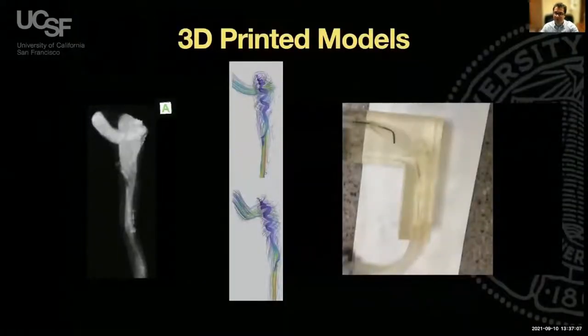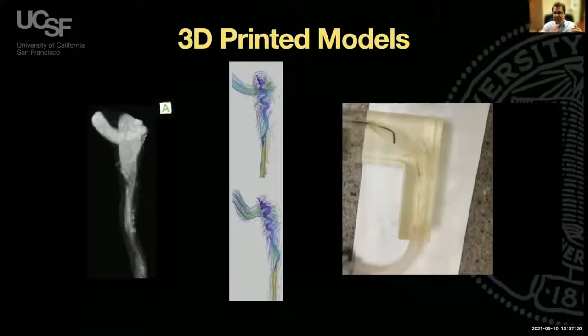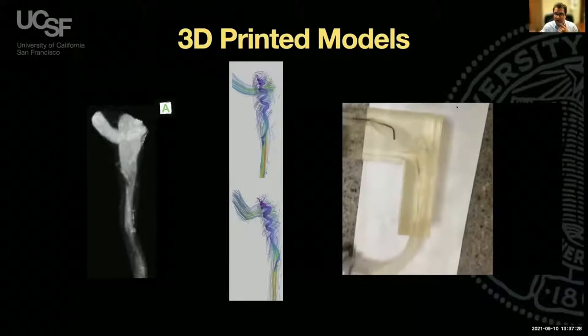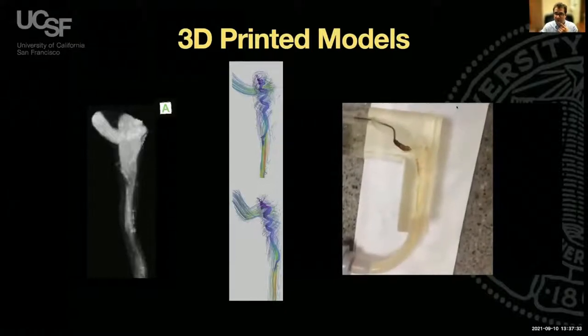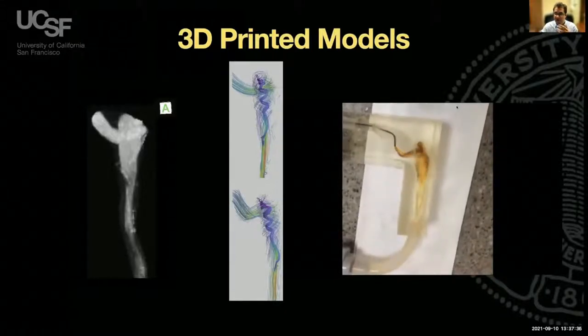We can also print 3D models of patient-specific anatomy and attach them to a flow circuit pushing a blood analog at the same velocity and heart rate as patients. We inject dye to validate the 4D flow and CFD results. You can see the center core helical pattern forming in this dye dilutional video of a 3D printed patient-specific model, confirming the accuracy of our computational results.